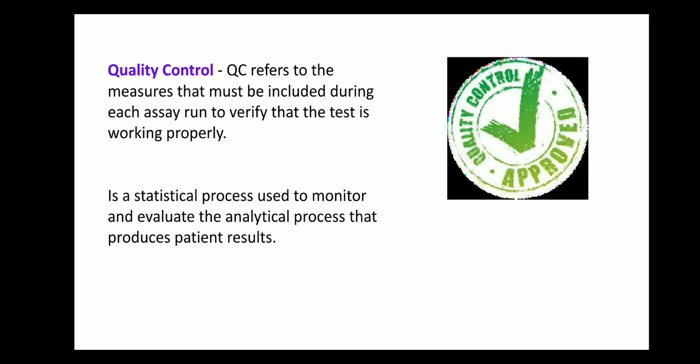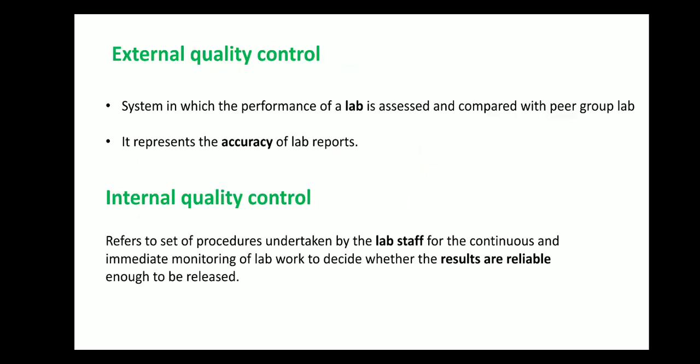Quality control means that during each assay run, we verify whether the test is working properly. So that is called quality control. It is a statistical process used to monitor and evaluate the analytical process and produce the patient result. There are two types of quality control: EQC, external quality control, and IQC, internal quality control.